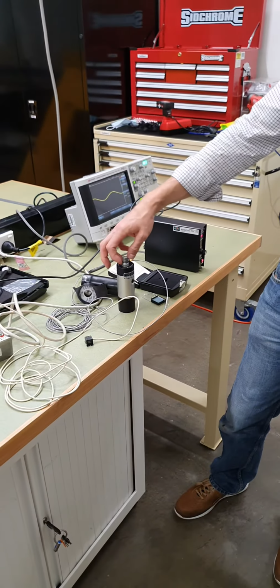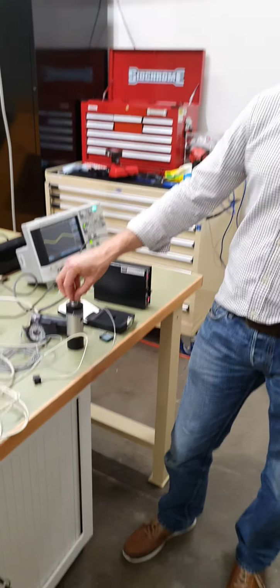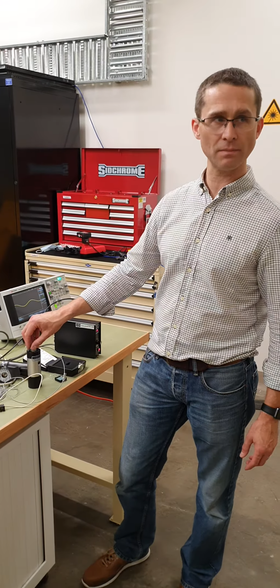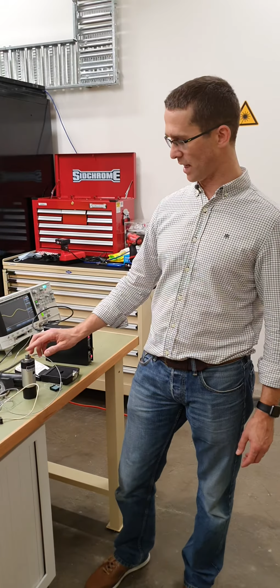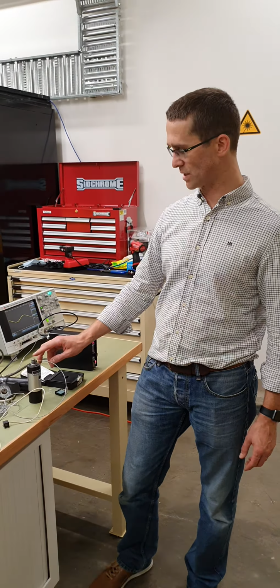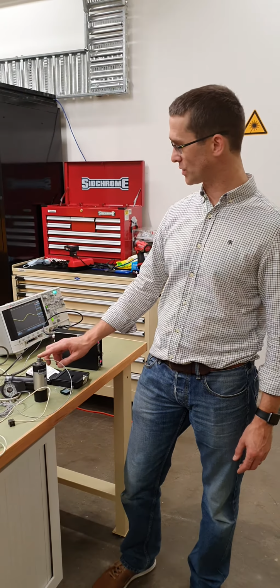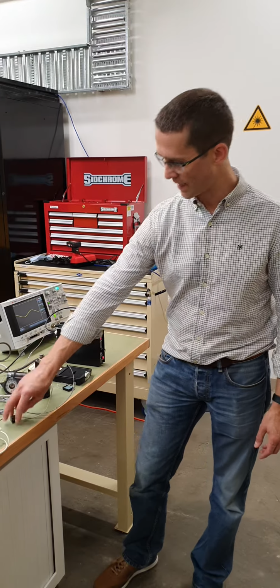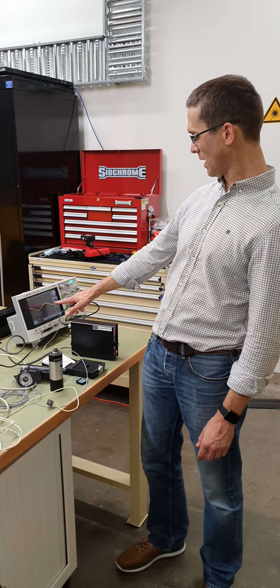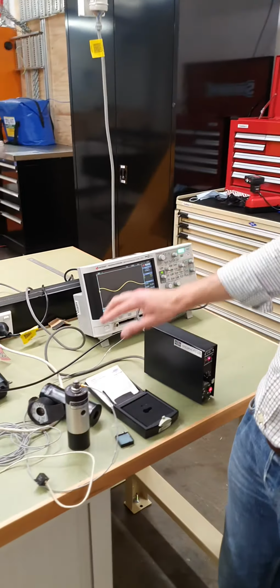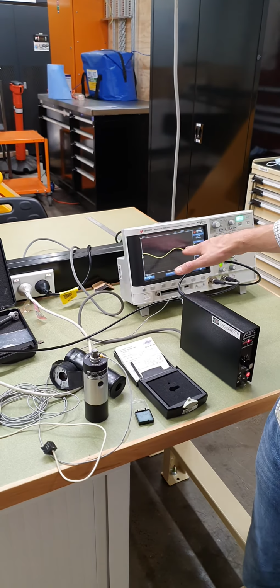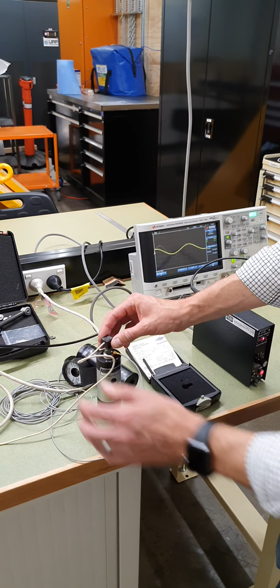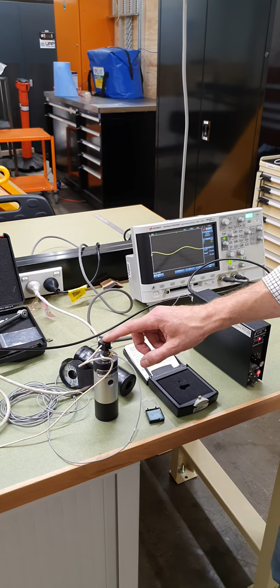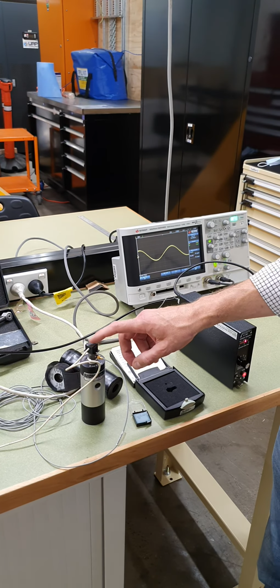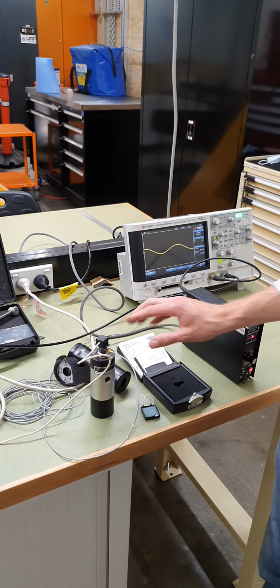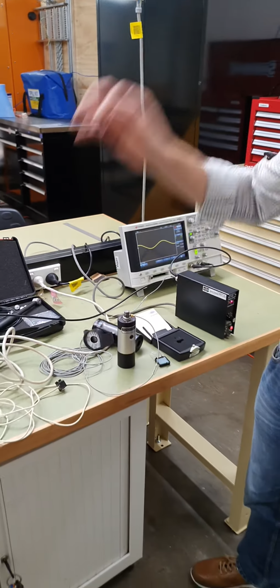It's got a built-in accelerometer such that no matter how much mass we attach to the top of it, obviously within sensible limits, it will always produce 10 meters per second squared, or 10 millimeters per second of velocity. So if I add, you can see here now we've got a measurement of a certain number of volts here, and we could confirm that that was 10 meters per second squared. But if I add some extra mass, eventually the device, you can see it adjusting the level. If I apply a force, it adjusts the level. Eventually it will again give us 10 meters per second squared.